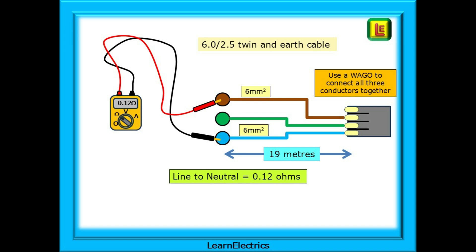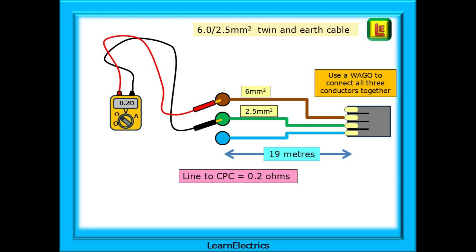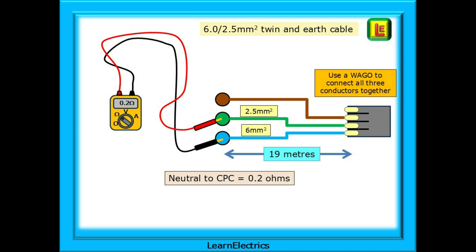Now we can low ohms measure between line and neutral, all at the consumer unit. In this example we have a measurement of 0.12 ohms. Here we are using 6x2.5 twin and earth cable and at 19 metres the low ohms resistance reading between the line and CPC returns 0.2 ohms. We would expect this as the CPC has a smaller cross-sectional area than the line and neutral and will therefore have a higher resistance. The neutral to CPC resistance check should be the same as the line to CPC — a reading of about 0.2 ohms.